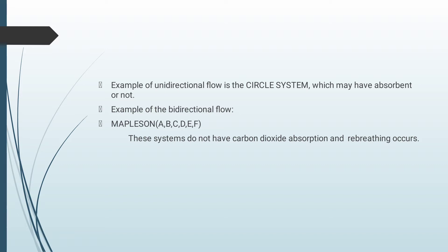An example of unidirectional flow is the circle system, which may have an absorbent or not. An example of bidirectional flow is Mapleson systems. These systems do not have carbon dioxide absorption and re-breathing occurs depending on fresh gas flow. Since there is no device for absorbing carbon dioxide, the fresh gas flow must wash out the carbon dioxide from the circuit. These systems are sometimes called carbon dioxide washout circuits or flow-controlled breathing systems because elimination of carbon dioxide depends on fresh gas flow. It is best to monitor end-tidal carbon dioxide to determine the optimal fresh gas flow.